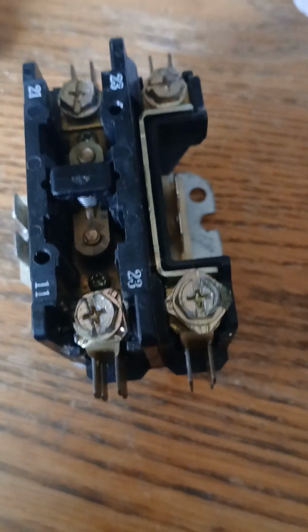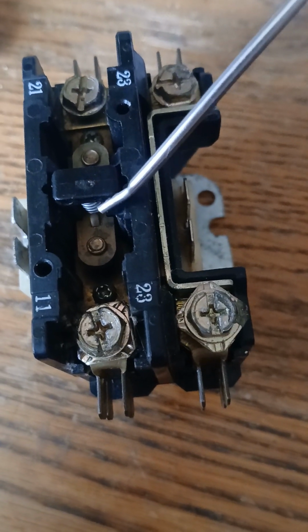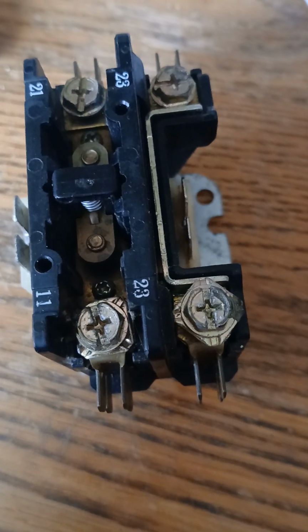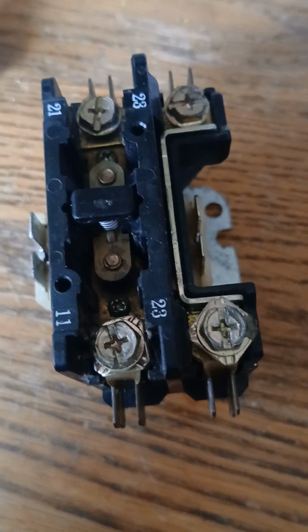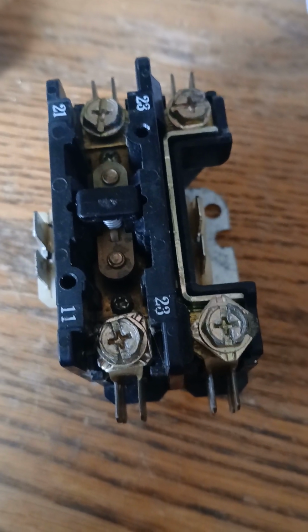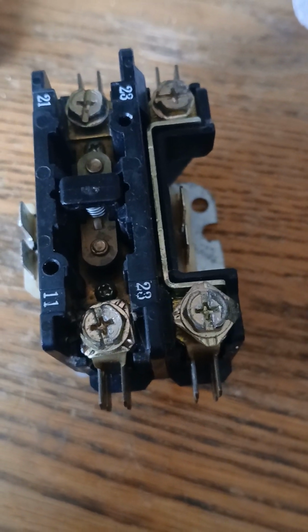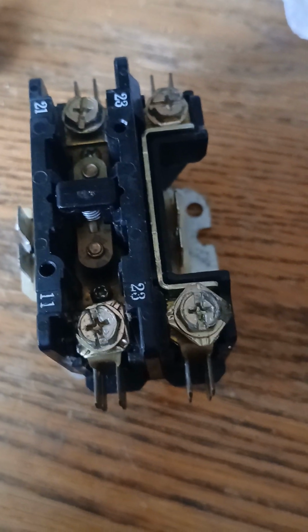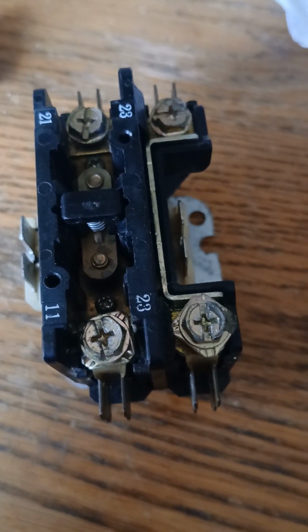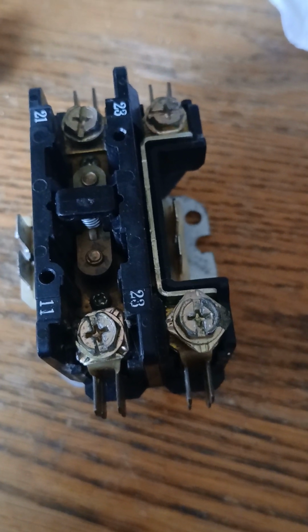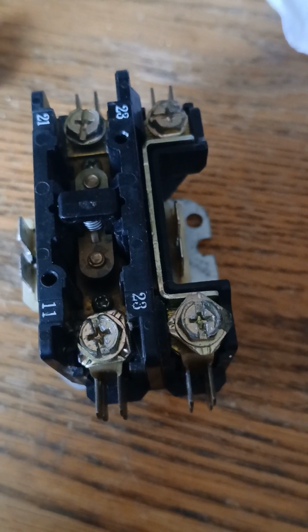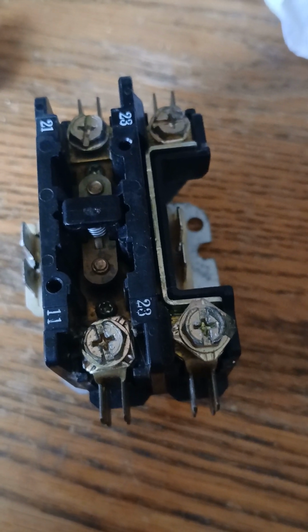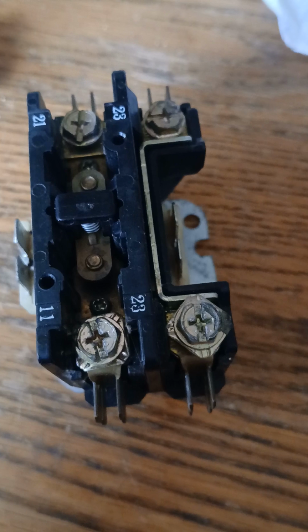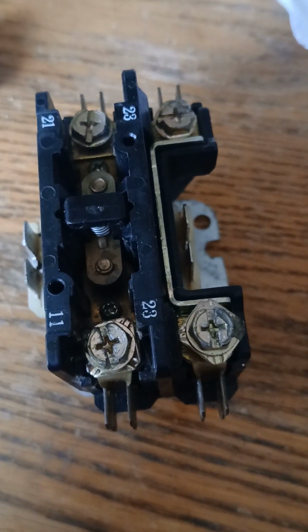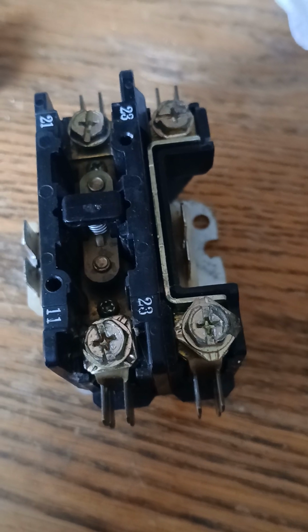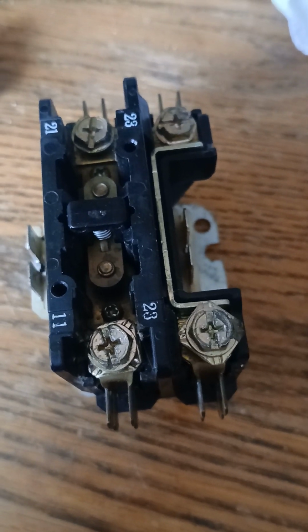So it's good to have it electronically, because if you do it manually, I guess it could be physically done manually, but hypothetically, let's just say there's no contactor here. We just hardwired this straight in. Well, then the compressor runs and the condenser fan motor runs, both run. Correct. However, if they just incessantly run, you need something to turn it off. And if you don't have anything to turn it off, then the compressor or the condenser fan motor could burn itself up. So basically, this is where the low voltage can help turn the contactor, so to speak, on and off.